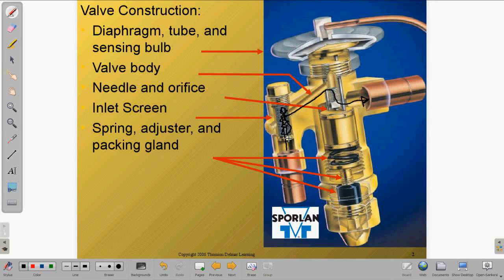So make sure that if you do have a TXV valve that's starving, before you replace that valve, you pull that screen out and look at it and clean it. It's always good to have an extra TXV valve on hand to make sure that if it is a bad TXV valve and the screen is clean, that you can replace it at the time, because it's a lot of work just to check this little screen right here.